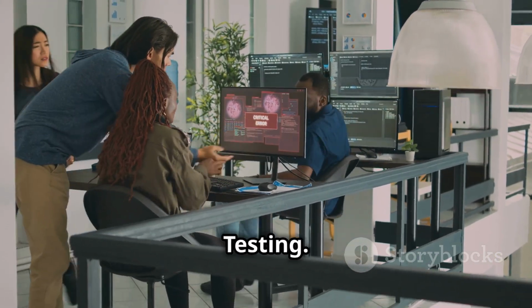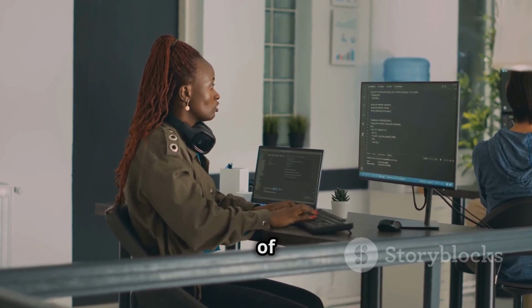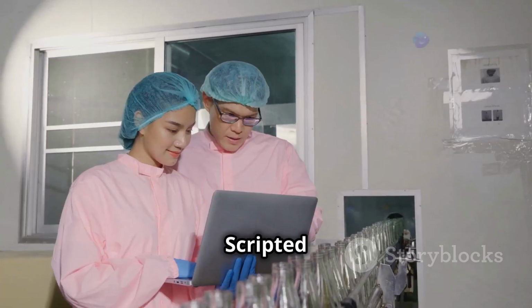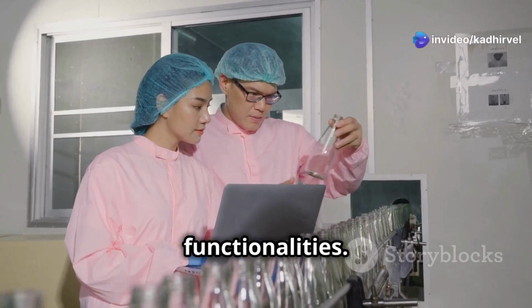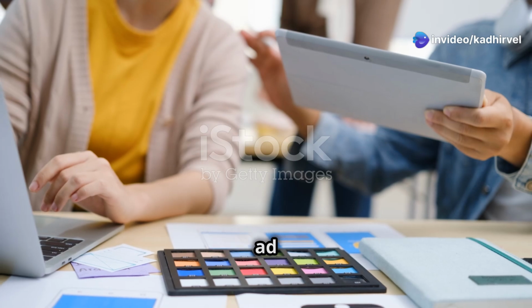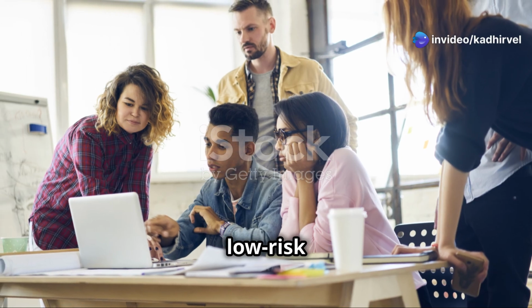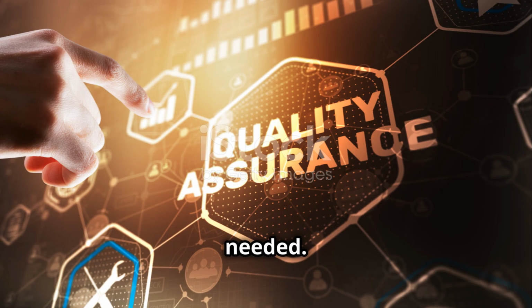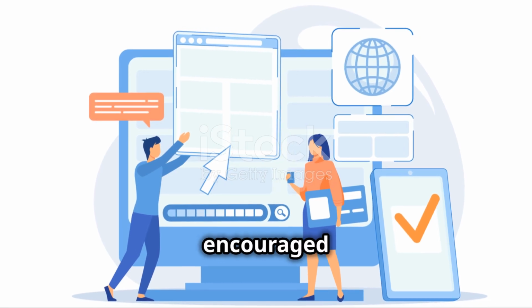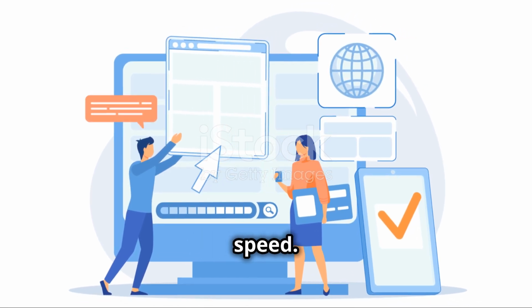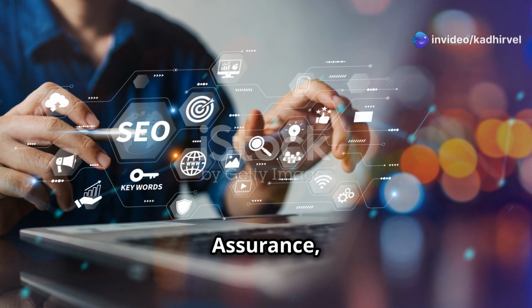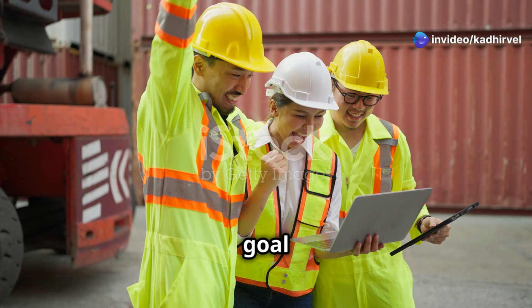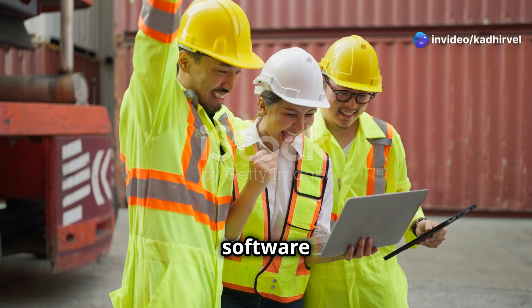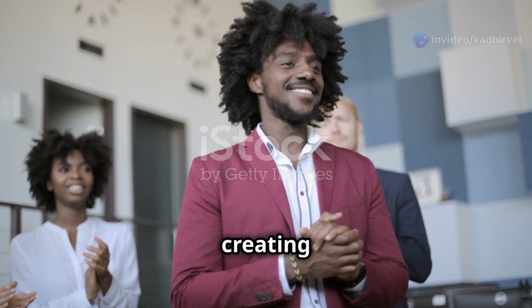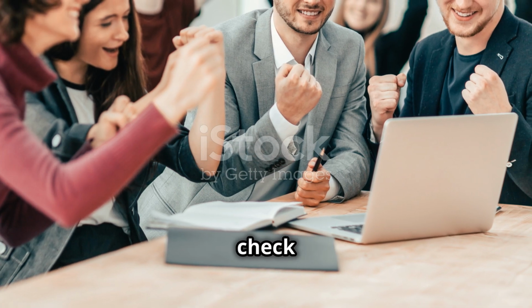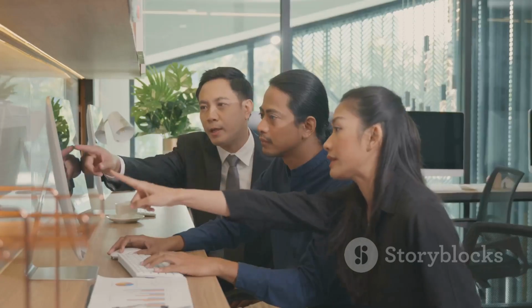Fourth, efficient testing. CSA promotes the use of modern testing methods. Scripted testing is for high-risk, critical functionalities. Unscripted or ad hoc testing is for medium or low-risk areas where formal scripts aren't needed. Automated testing is encouraged to improve efficiency and speed. And finally, the focus on assurance, not compliance. The goal here is to provide assurance that software performs as intended, rather than creating excessive documentation just to check boxes for compliance.